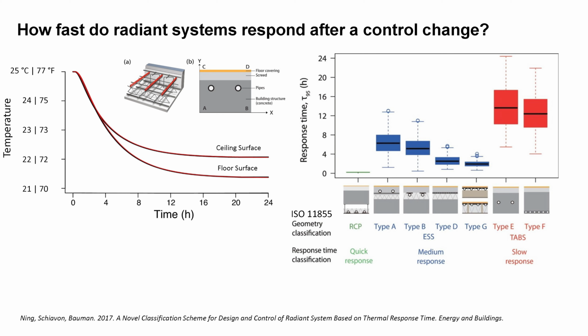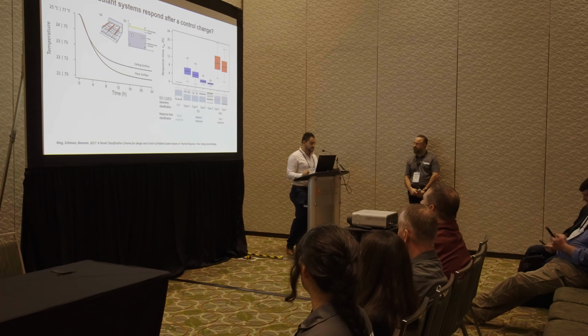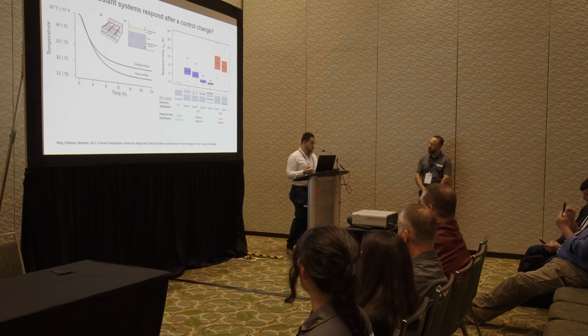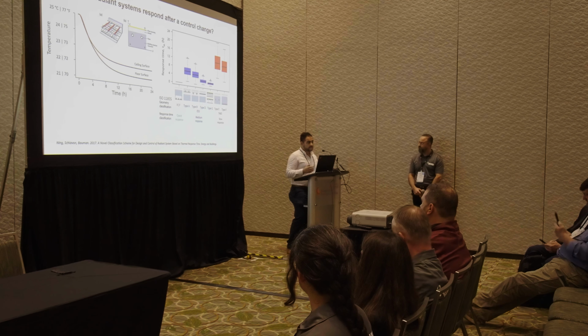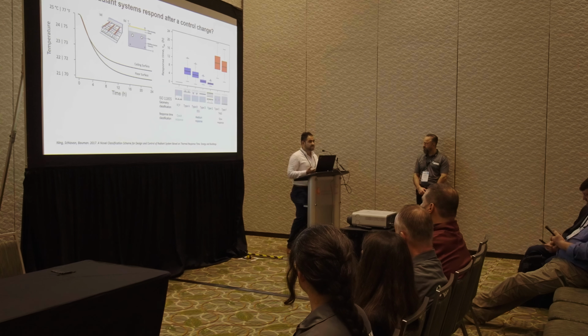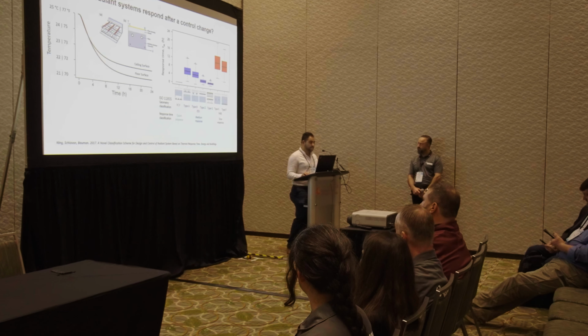On the left-hand side plot, you see that it takes more than 12 hours to cool down surfaces from 77 degrees to 72. And the right-hand plot just shows you a distribution of these response times for various design parameters for these radiant systems. It shows that embedded surface systems have a median response time of 6 hours, while thermally activated building systems have 14 hours. So it's really hard to control them or to predict control strategies that will maintain a thermally comfortable environment in the indoor space.